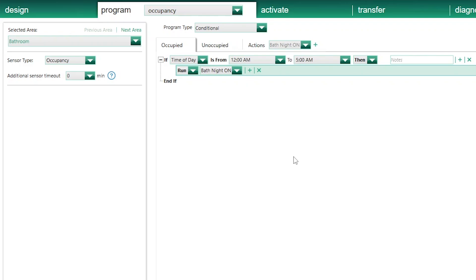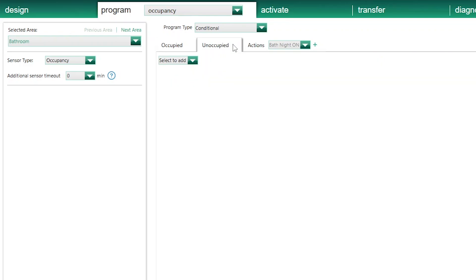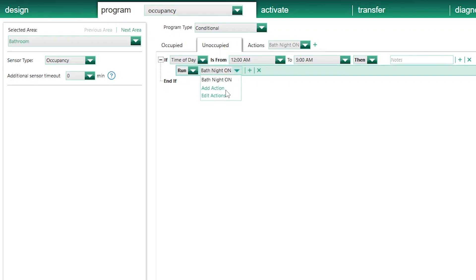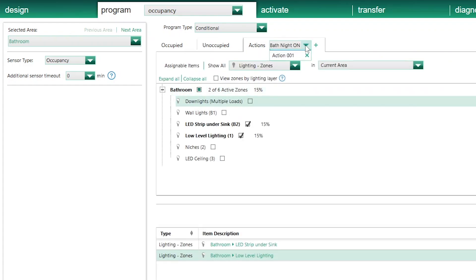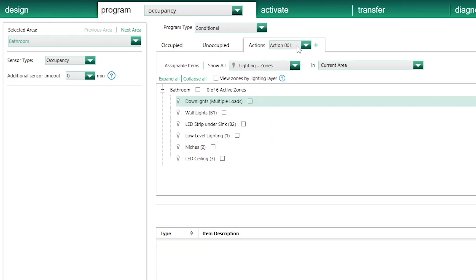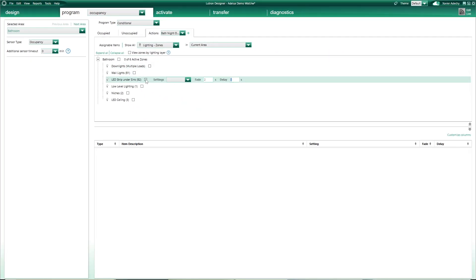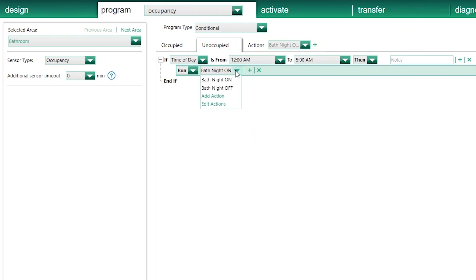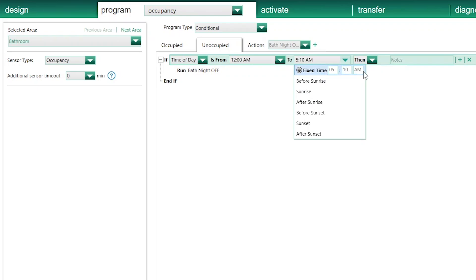And what happens when I leave the bathroom? For this, I go to the Unoccupied tab and do the same thing. If time is between midnight to 5 a.m., I'll run a new action. I click on Add New Action, then click on Edit Action to customize it. I change the name to Bath Night Off, which will turn off those two lighting circuits. Then I go back to the Unoccupied tab and make sure to select it. And if I'm really concerned about what happens if I walk in the bathroom just before 5 a.m. and exit after 5 a.m., here in the Unoccupied tab I can change the cutoff time to 10 minutes past 5, which should be good enough.